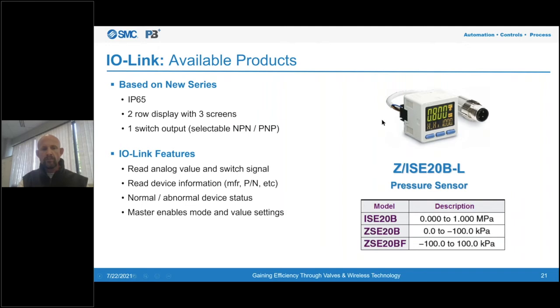In addition to the IOLink capabilities, it also has onboard one switch output. For traditional digital I/O systems, you can wire that output in, and it's selectable between PNP and NPN. What the IOLink features on this product do is allow you to read the analog value directly from these sensors through the IOLink network. You can also get the switch signal, so if you want digital set points, you can obtain that output information as well.